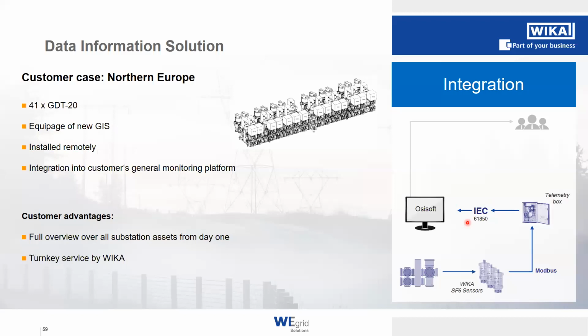So here the huge advantage is that the customer will have from day one of the GIS in operation a complete overview over all their assets, over their complete substation and their GIS and SF6 values. So they will be able to fully track what's going on with their substation. And here also we were able to provide a full turnkey service. That means from the beginning of the positioning of the sensors, laying the cables, designing everything, installing and commissioning the electrical equipment.